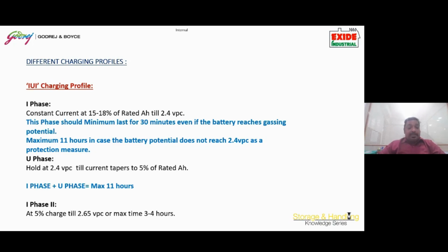So this is the I phase, and then comes the U phase, the hold phase. We hold at 2.4 VPC till the current tapers to 5% of the rated Ah capacity. So what we are doing here is that we start with 15 to 18% till we reach 2.4, and then we allow the current to taper down to 5% at 2.4 VPC. Together, the I phase and U phase should take a maximum of 11 hours of charging, or maybe 10 hours of charging.